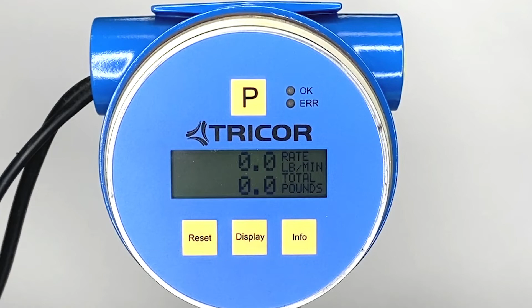Completing the 0-point calibration of your meter is the single most important step when setting up your meter for the first time. Essentially, you're setting the no-flow conditions for the transmitter. We recommend using the 0-point calibration when your system is closest to the actual operating conditions, particularly in terms of temperature.